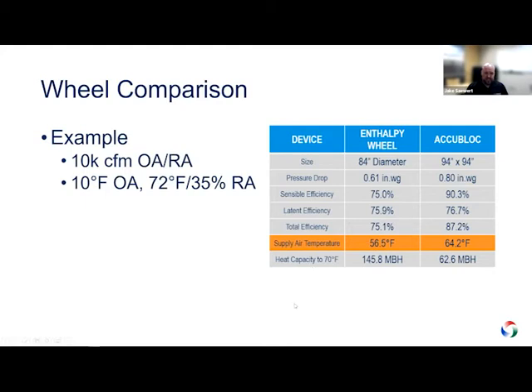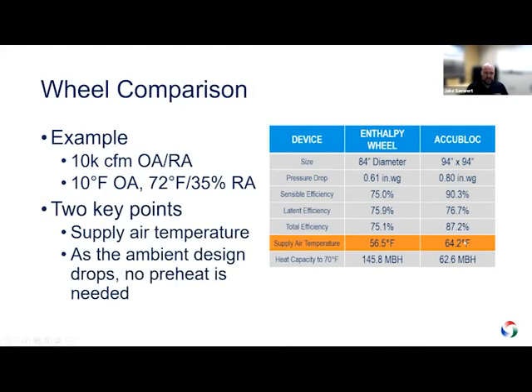The thing that really stands out that I always like to show people, however, is the supply air temperature. So that wheel at 10 degrees is going to get you to about 56.5 degrees. That's going to be cold. If you dump that straight into a space, it's going to need to be tempered. It's going to be too cold in winter. With the ACCUBLOC, we're getting all the way up to 64 degrees. You're getting close to the point where maybe you don't need much, if any, mechanical heat from your ventilation air. You might be able to do it actually with whatever you have going on in the space if there's a decoupled system.